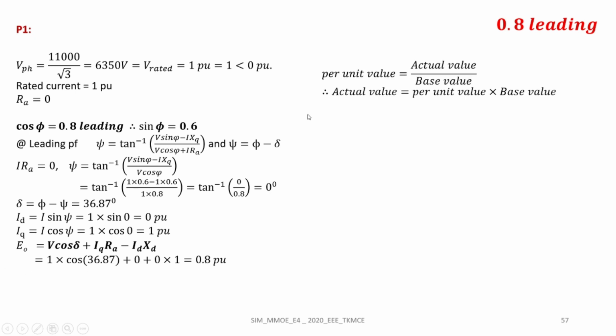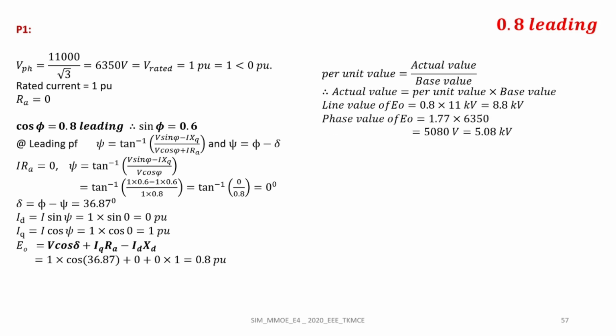We know per unit is equal to actual value by base value, and actual value is equal to per unit value into base value. Therefore, the line value of E0 is equal to 0.8 into the base value, that is 11 kV. The actual line value of E0 is obtained as 8.8 kV. Similarly, the actual phase value of E0 is obtained as 5.08 kV. Now, voltage regulation is equal to (E0 minus V) by V. It is coming as minus 20%.